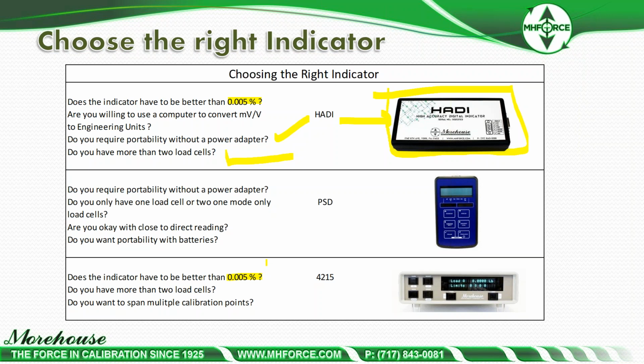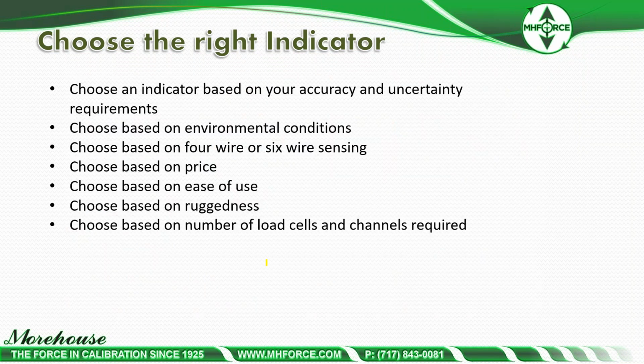Do you have more than 2 load cells? Do you want to span multiple calibration points? That's a good indicator for that. But when you're evaluating things, you choose an indicator based on your accuracy and uncertainty requirements, based on environmental conditions, based on 4 or 6 wire sensing, and based on price. I mean, everybody's looking for price. That HADI unit really stacks up with some of the best indicators. It's a very good value 6 wire system. Choose based on ease of use and ruggedness.